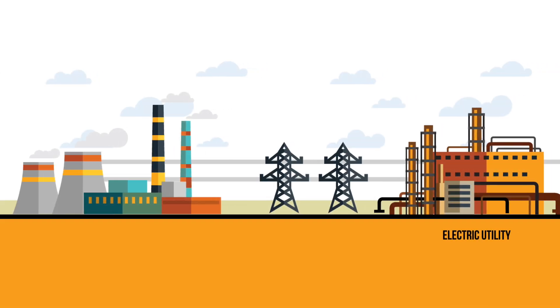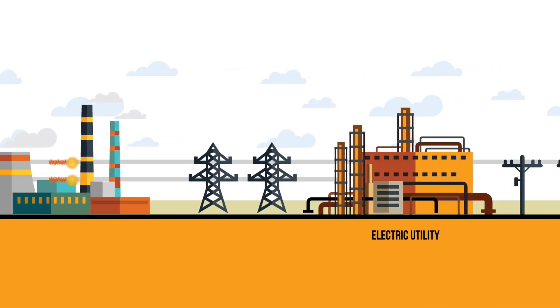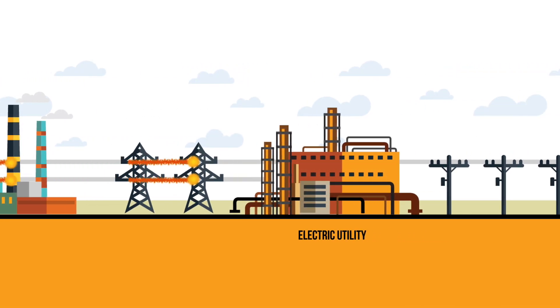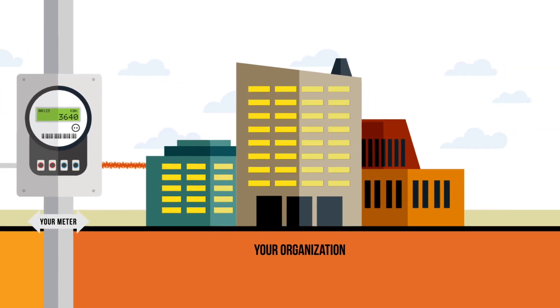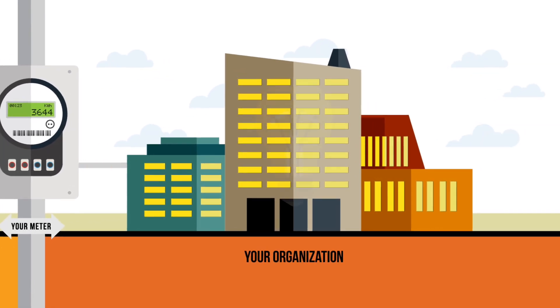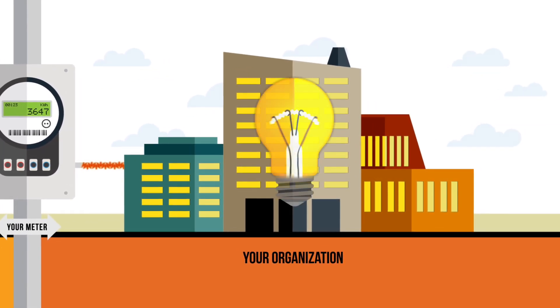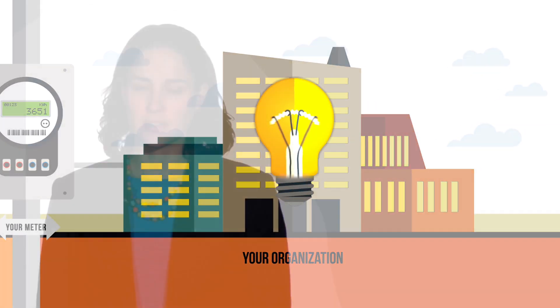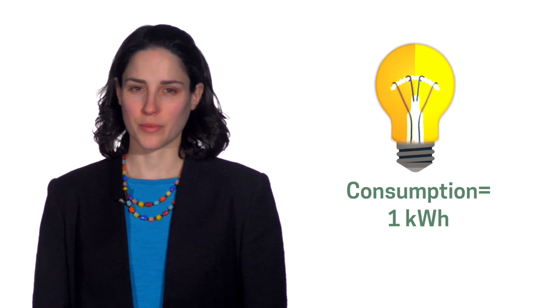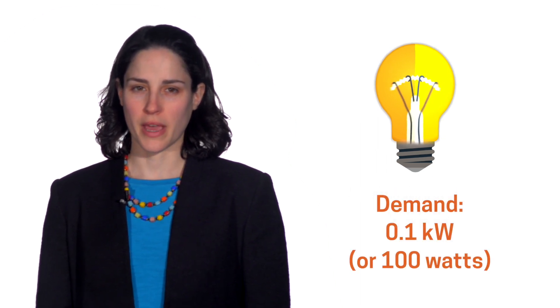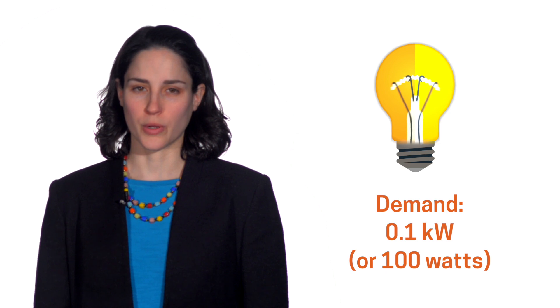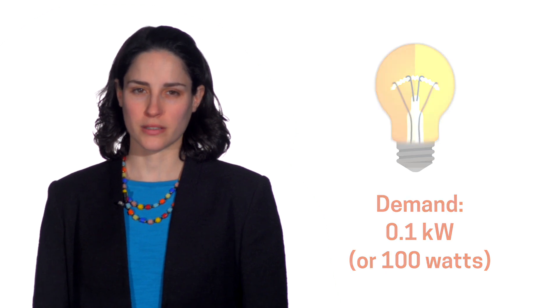The utility must be ready to deliver that 0.1 kilowatts of electricity whenever that bulb is switched on. In this single bulb scenario, our light is on for 10 hours. Our consumption is 1 kilowatt hour of energy, yet our demand remains constant at 0.1 kilowatts.